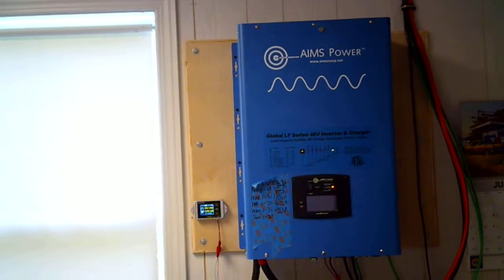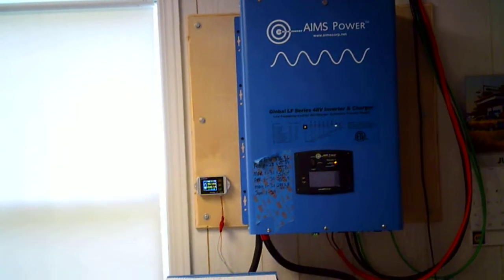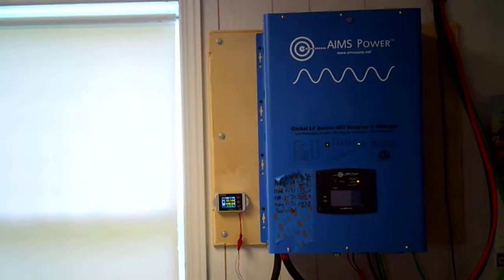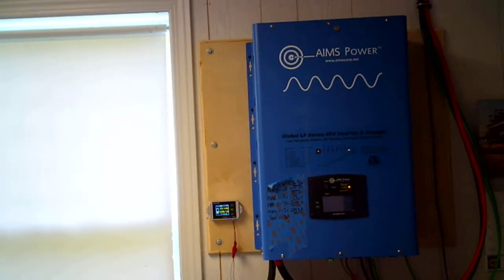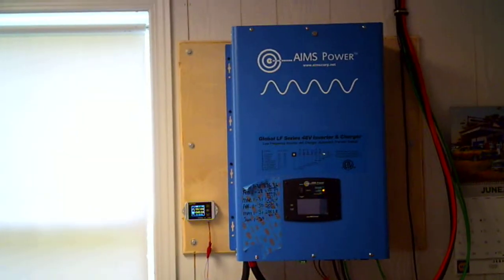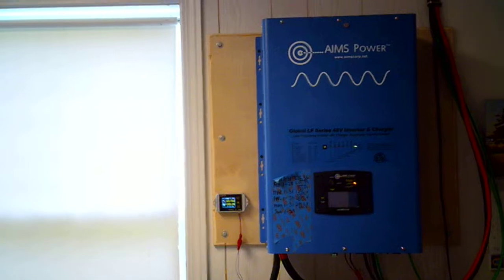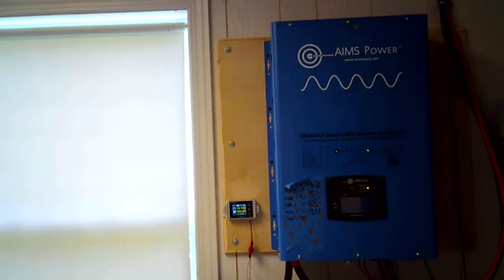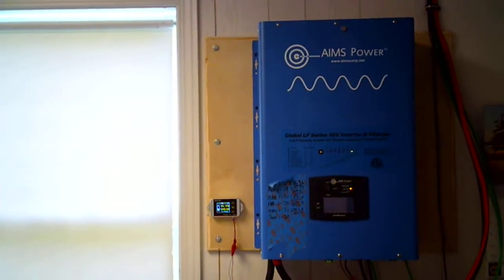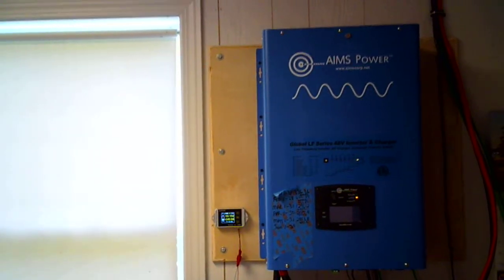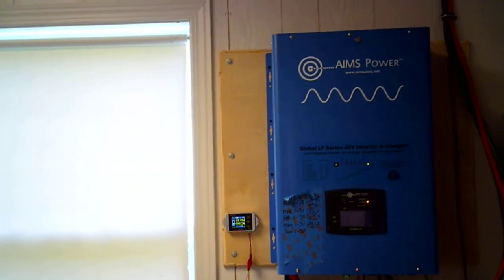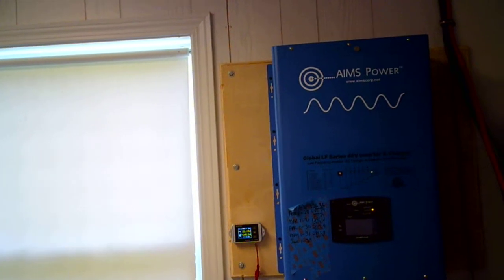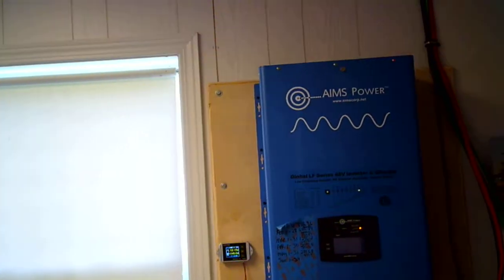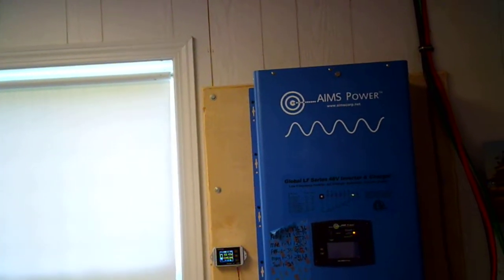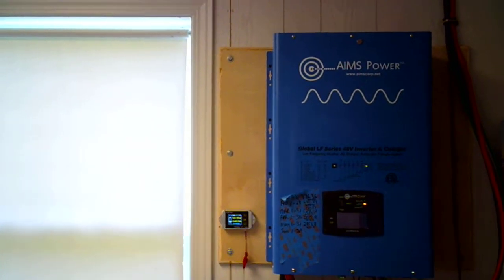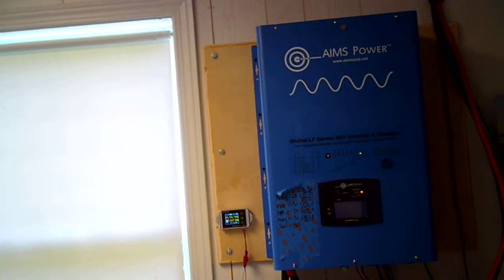The electric smart car I've got has its charger turned down, so it pulls about 45 amps too. The water heater pulls about 100 amps, the clothes dryer pulls about 100 amps, and the well pump when running is about 45 amps, but during startup it can pull well over 130 amps. So you can see if I've got both cars charging, that's 90 amps, then the dryer's on for another 100 - that's 190 - then somebody takes a shower and the water heater kicks on for another 100 amps, and it overloads everything pretty quickly.